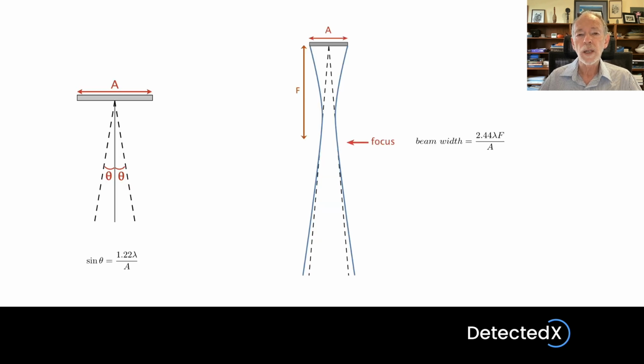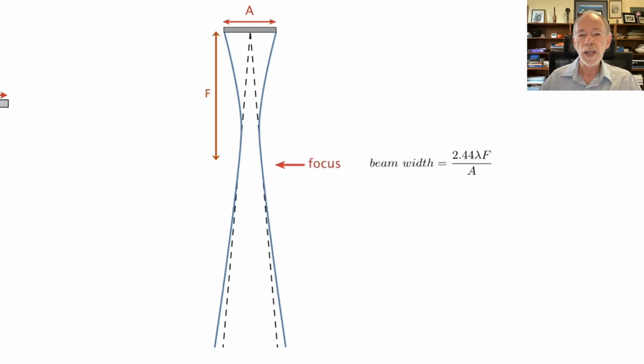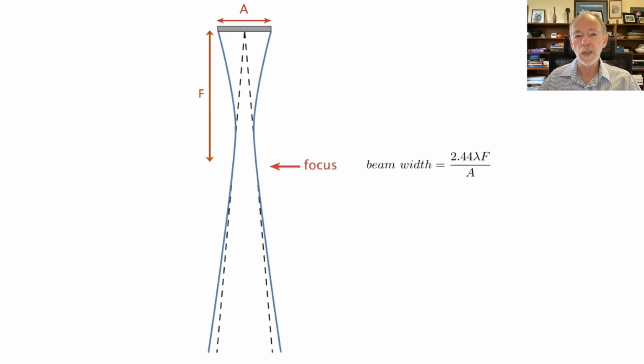Now we're going to look at the way in which the machine focuses the ultrasound beam and the nature of that beam. You'll notice on the right-hand side that I've drawn a focused ultrasound beam. I've marked two important parameters: the size of the transducer, which we refer to as the aperture, A, and then the depth of focus, which is the depth at which the beam is actually being focused, which is going to be the narrowest part of the beam, and I've labelled that F.